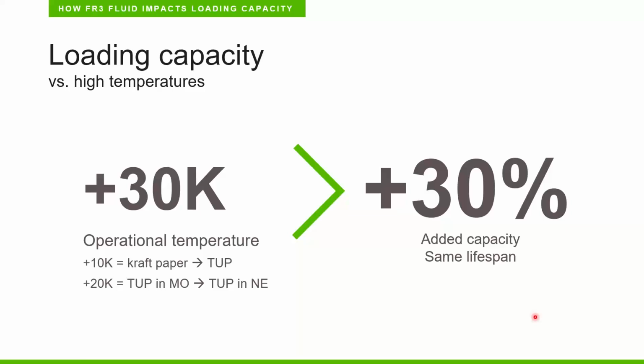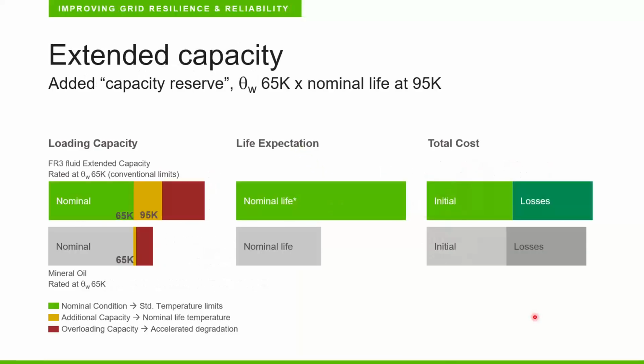Of course, it's a little bit conservative rule, and designing a transformer is something much more complex than what I'm saying here. But it gives us an idea that this FR3 fluid with the paper, with increased temperatures, which is also accepted by standards, gives us a plus 30 degrees increase on the operational temperature. And this can lead to an increase of 30% in the added capacity. And if we can move to the next slide, I want to put this in some perspective. If we see two lines, the upper one in green is a transformer designed and filled with FR3 fluid, and the lower one is the same transformer filled with mineral oil.